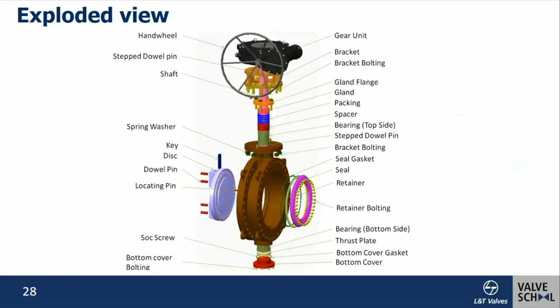This is an exploded view of the triple offset butterfly valve. The components include the body, a disc, and a laminar seal fitted onto the disc using a retainer. It has a single-piece shaft, and a gland-packing arrangement similar to a gate valve or globe valve. The shaft bottom is fitted with a thrust plate retained by a retainer bottom cover plate. This gland packing and bottom cover arrangement keeps the internals safe and makes it truly a metal-seated valve comparable to a gate valve, avoiding emission to the atmosphere. The operating arrangement is a quarter-turn.